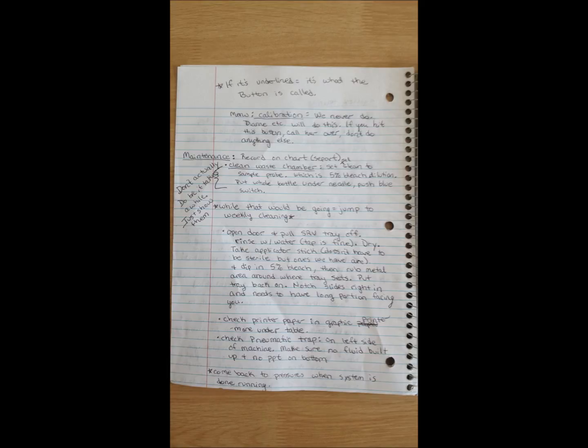The number one thing about analyzers is they like to be clean, but not too clean. What we're gonna do, I'm just gonna take an applicator stick, and the ones I have happen to be sterile. It doesn't really matter. Dip it in your Clorox, because if you notice, this is really gooey. We're gonna clean all that gooey off of there. We don't want gooey buildup because then it gets into our analyzer and makes a mess. So you're going to take as many of these as you need. Get that clean, and at the end just wipe it with some water.